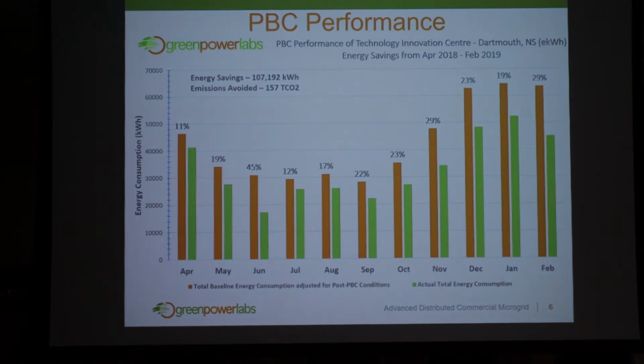In terms of how we're saving energy, we run a couple of models. One looks at an optimized morning startup process: using weather data, we model the building in a 3D environment and how it responds to outside conditions as well as occupancy inside. From that we determine the best time to start ramping the different devices, doing a staged ramp, which also helps mitigate the demand charge. We also have an operating mode—once the building is occupied, thermostats are programmed so if you don't like the temperature in the space, you can adjust it warmer or cooler, and our application picks that up. We're reading from the system every 15 minutes and writing every 15 minutes as well.